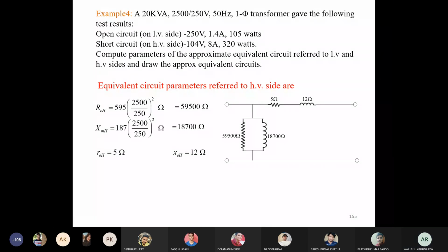Sir, when referred to the high voltage side, the resistance and reactance, REH and XEH, they should come first and then the parallel circuit, right? See, I have already mentioned at the very beginning of this chapter that there is no such primary or secondary. While you are supplying to the low voltage side and taking output from the high voltage side, then the low voltage side is the primary side and the high voltage side is the secondary side. But when you are giving supply to the high voltage side and taking output from the low voltage side, then the high voltage side is the primary side and the low voltage side is the secondary side, isn't it? So here in this circuit, we are considering the high voltage side as the primary side.